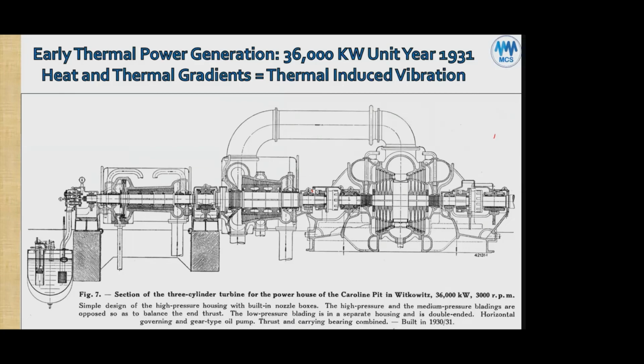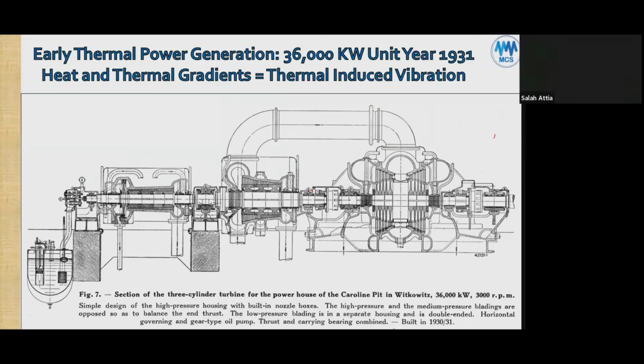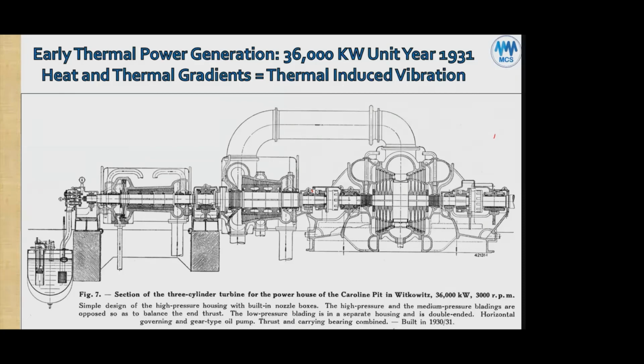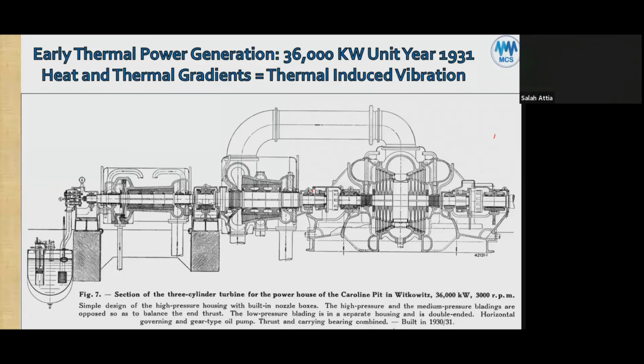So you'll get a turbine, let's say it's 7,000 RPM, and let's say the shaft diameter at the bearing is 5 inches, or if you want to talk in millimeters, that would be 125 millimeters, for example. And the bearing clearance, the diametral, we call it diametral, so we're not talking radial clearances, we're talking diametral clearance, meaning total clearance between the shaft and the bearing. It should be on a steam turbine roughly 1.25 or 1.2 times diameter over 1,000. Yes, that's correct. The cold clearance.